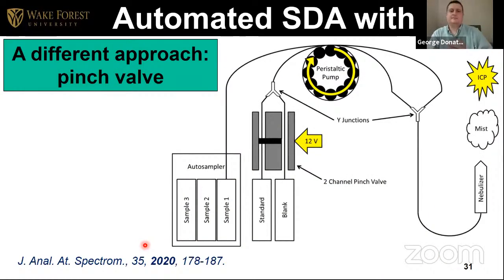Then a final method that we tried to improve on that one. The main trouble with the previous method is it takes a little while. It takes about 6 minutes per sample, so it's a little longer. So we tried to do it even better and more automatic. We use a pinch valve here, and the idea is that the pinch valve does the mixing of standard and blank. The sample comes from the autosampler and goes to the ICP. Then for standard and blank, when the switch valve is in this position, the blank is open, and you move this every 60 seconds. So when you move this, you go from total blank to total standards in every cycle. And then this mixes with the sample there. The sample will still have the same amount of sample, but increasing concentrations of standard.